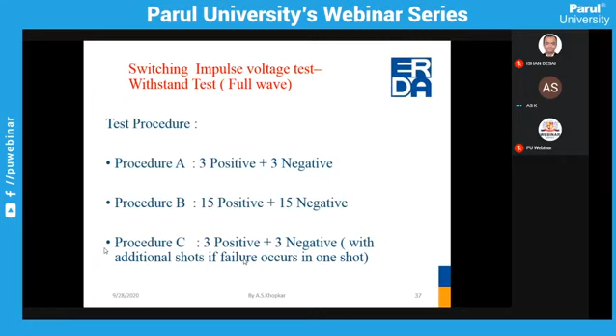Okay, so this was about the high voltage testing of power frequency, switching impulse voltage withstand test and lightning impulse. Now again, as I told you, the partial discharge test is also conducted in the laboratory. This test is conducted as a routine test, not a type test. Earlier we have seen the lightning impulse and switching impulse, those are conducted as a type test. And the power frequency test we conduct as a routine test.